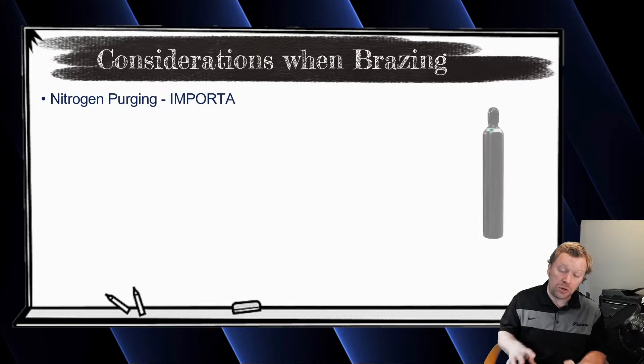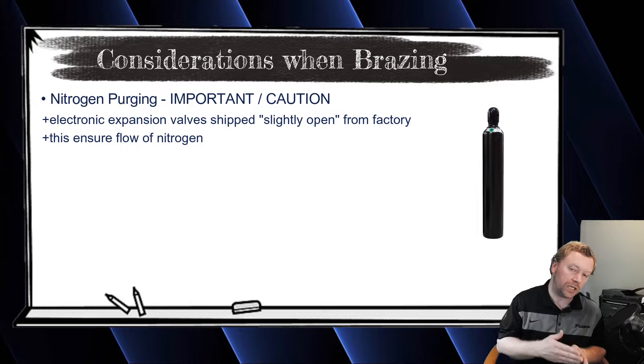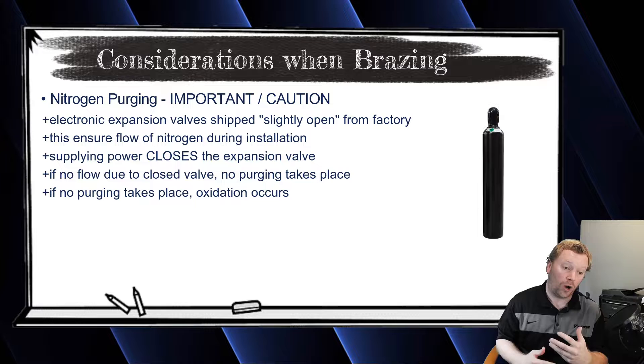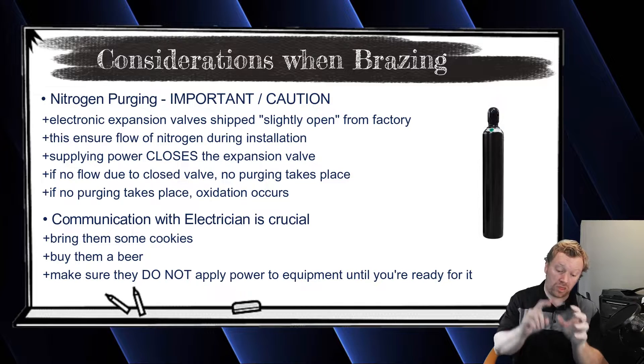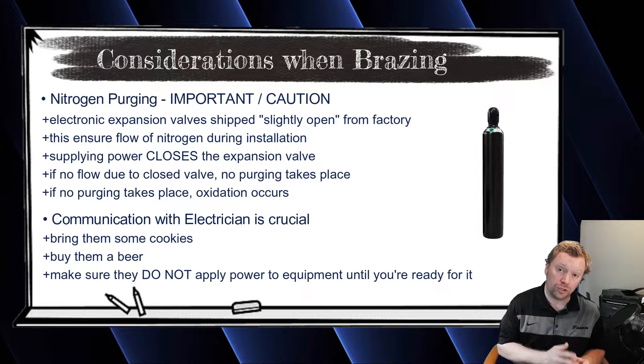When it comes to purging, here's a huge alert: all the EEVs are manually cracked open from the factory, but if your electrician applies power to an indoor unit, that EEV is immediately driven shut. Whoever's installing this VRV system needs to communicate with the electrician — do not apply power to any of my equipment until I'm completely done with the piping: purging, brazing, pressure test, evacuation, and refrigerant addition. Then you can test your power connections.